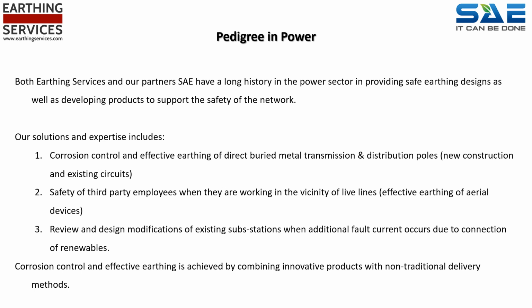corrosion control and effective earthing of direct buried metal, transmission and distribution poles, safety of third-party employees when they are working in the vicinity of live lines, review and design modifications of existing substations when additional fault current occurs due to connection of renewables. Corrosion control and effective earthing is achieved by combining innovative products with non-traditional delivery methods, such as volumetric mixers being used in North American installations, where the material is mixed as it leaves the truck, so there is no waste and holes are backfilled in minutes.